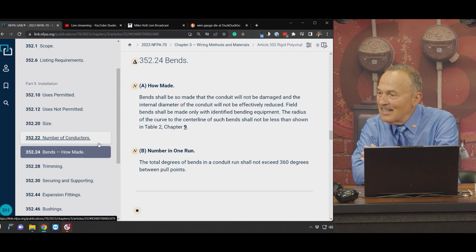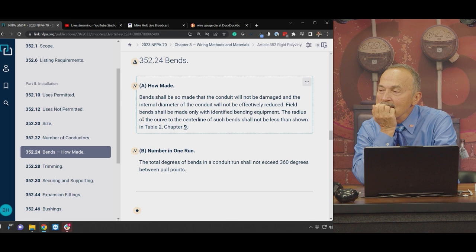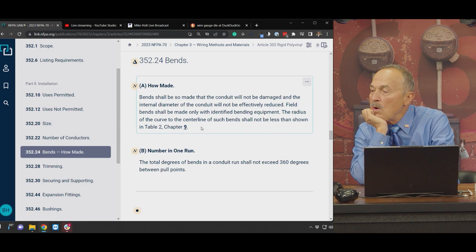As long as we're on a roll, it's also 352.24A — bends. Bends shall be so made that the conduit will not be damaged and the internal diameter of the conduit will not be effectively reduced. Field bends shall be made only with identified bending equipment. The radius of the curve to the center line of such bends shall not be less than that shown in Table 2, Chapter 9.